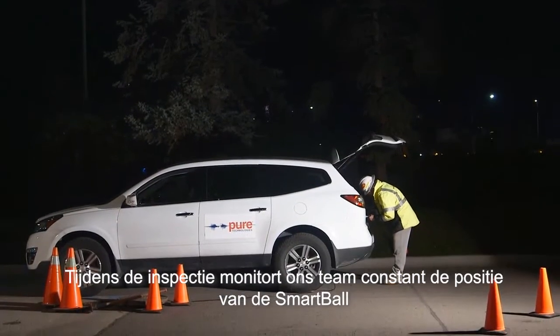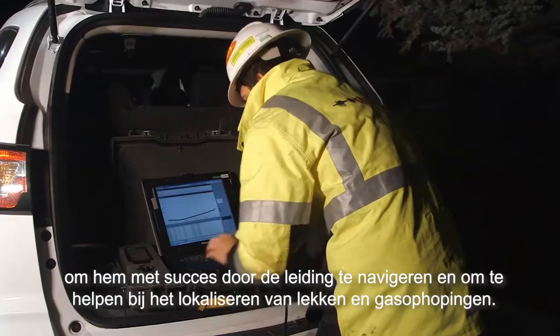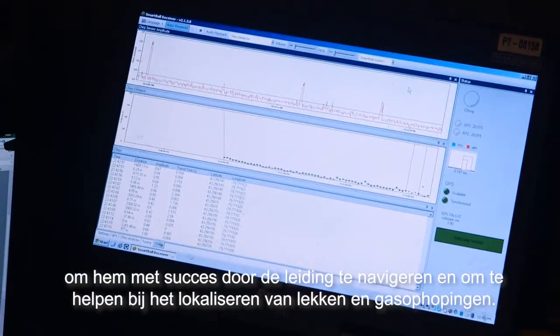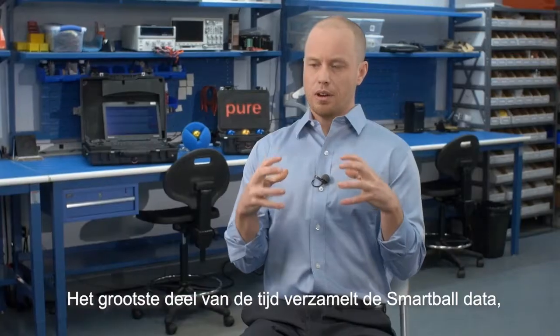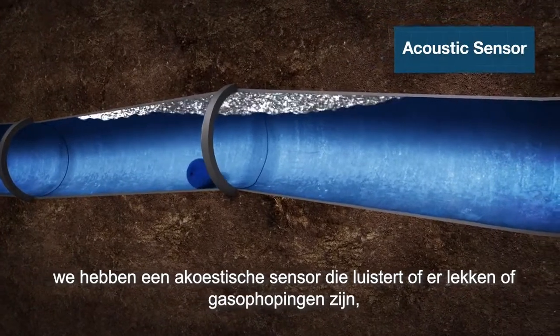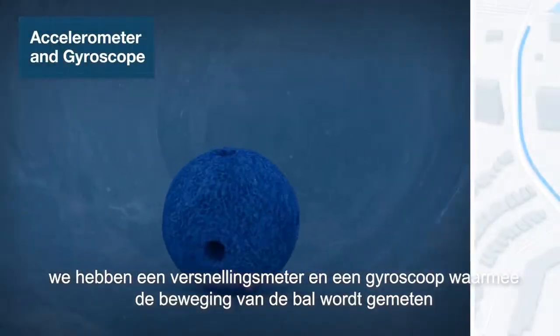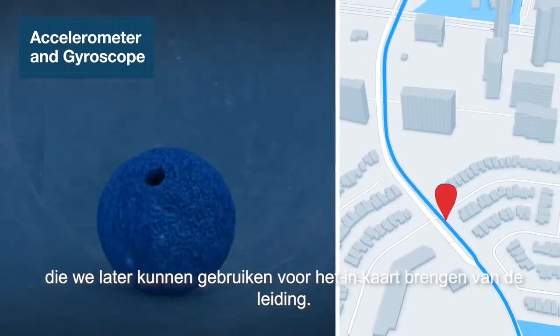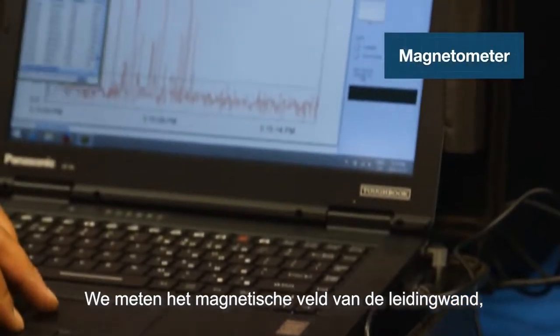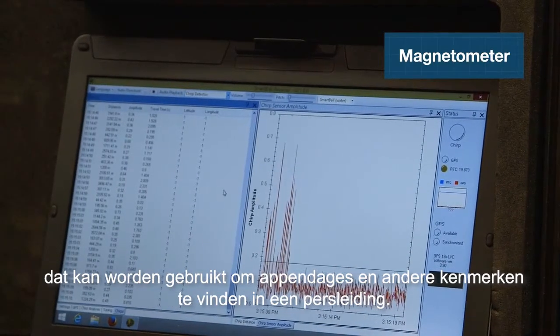Throughout the inspection, our team is constantly monitoring the position of the SmartBall to successfully navigate the pipeline and to assist with locating leaks and gas pockets. The SmartBall is collecting data: we've got an acoustic sensor that's listening for leaks and gas pockets, an accelerometer and a gyroscope measuring movement of the ball that we can later use for pipeline mapping, and a magnetometer measuring the magnetic field coming off the pipe wall that can be used to find appurtenances and other features in a pipeline.